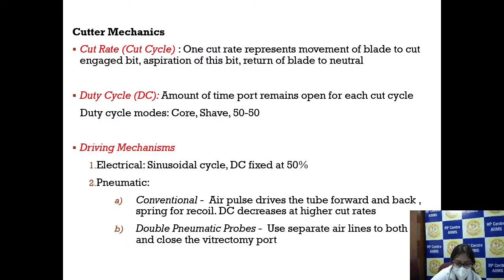So the driving mechanism which I told in vitrectomy probes is the electrical, where the duty cycle is fixed at 50%, whereas pneumatic comes in two types. The conventional type where we have a spring for recoil, and the double pneumatic probes where we have a dual pneumatic chamber which helps the diaphragm to go back into the normal position. So this is a conventional spring based vitrector. You can see a spring is there. Usually in the spring based cutters, the cut rate cannot increase so much because of the spring, so it can reach only up to 2500 cuts per minute.